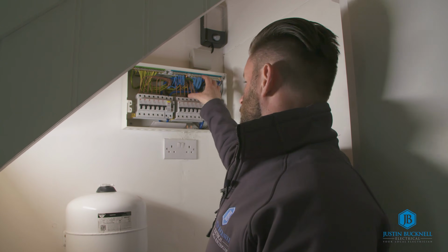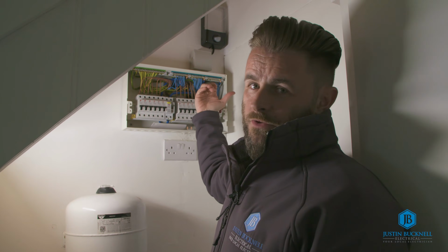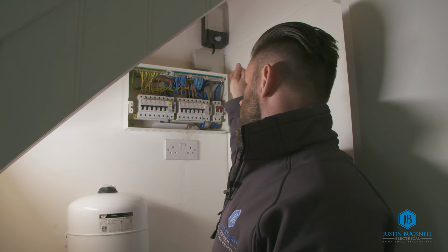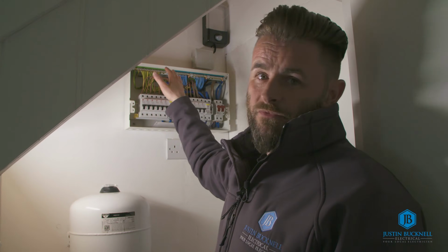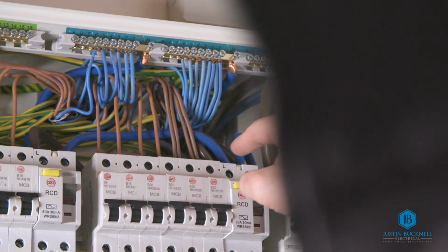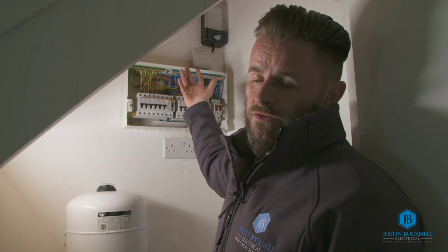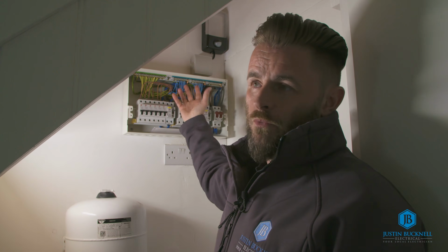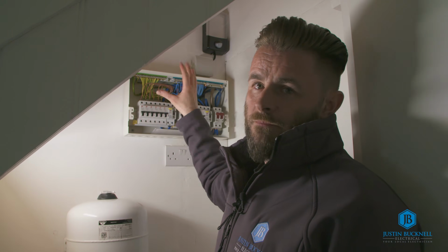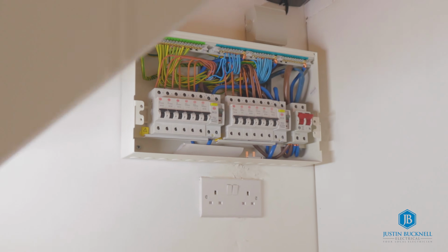However, where the cable entries come into the back of the consumer unit, I can see straight into the cavity in the timber frame of this timber building. So what I really would like to have seen is some fire foam in there, so that will be picked up on the remedial works, and we'll get that filled with some fire foam when we come back round to do the remedial works there.